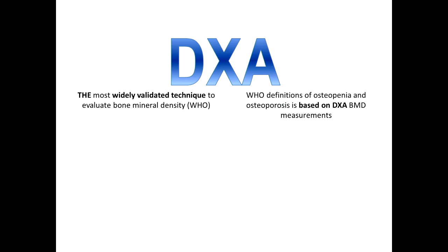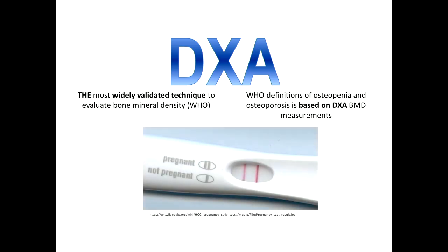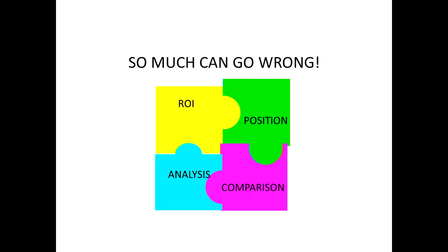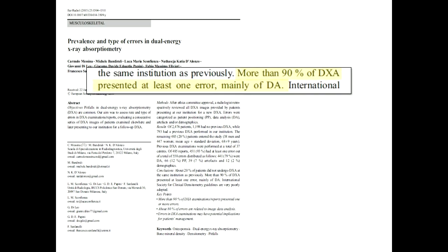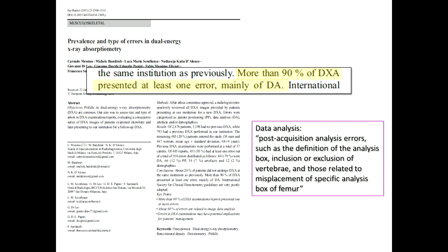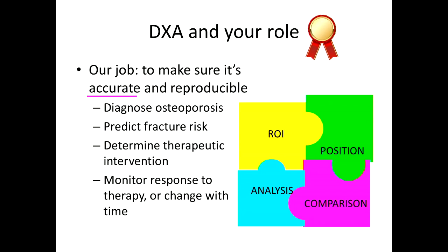DEXA is the most widely validated technique to evaluate bone mineral density, and the World Health Organization defines osteopenia and osteoporosis based on DEXA measurements. However, a study in European Radiology in 2015 found that more than 90% of DEXA exams had at least one error, mainly in data analysis. Therefore, it's our job to ensure that DEXA is accurate and reproducible so that we can diagnose osteoporosis, help predict fracture risk, determine therapeutic intervention, and monitor response to therapy over time.